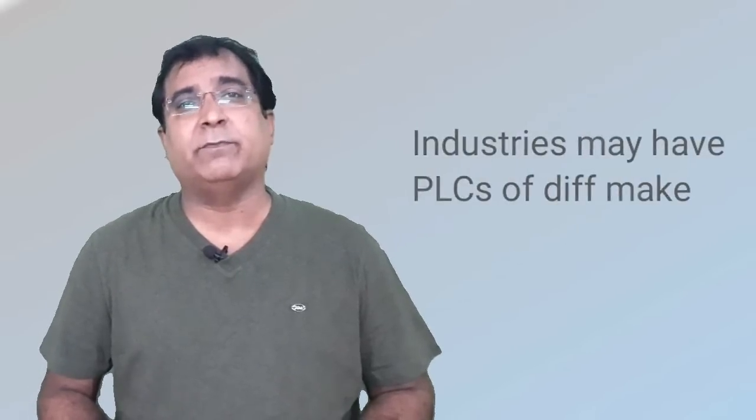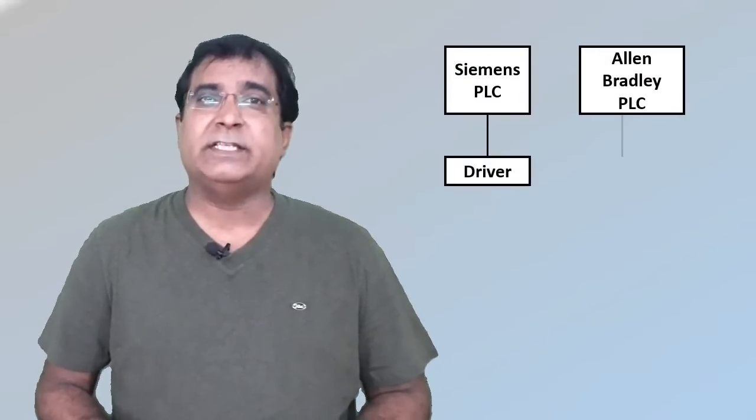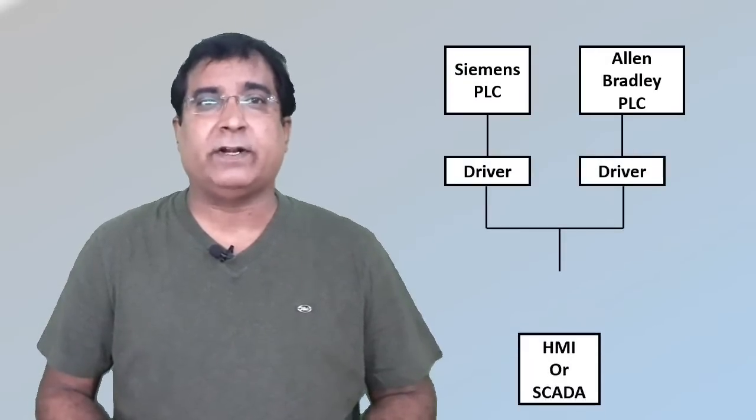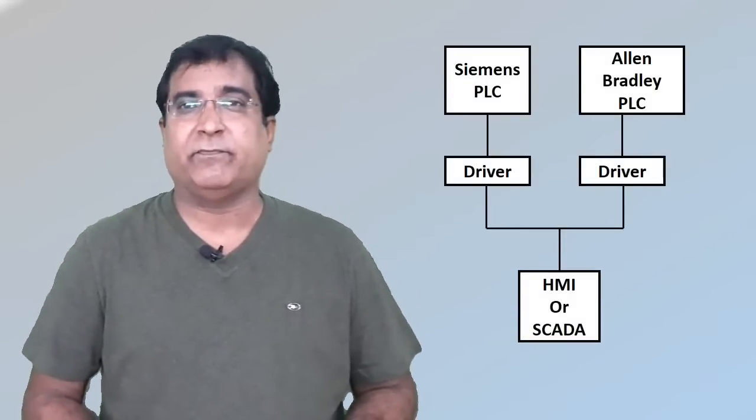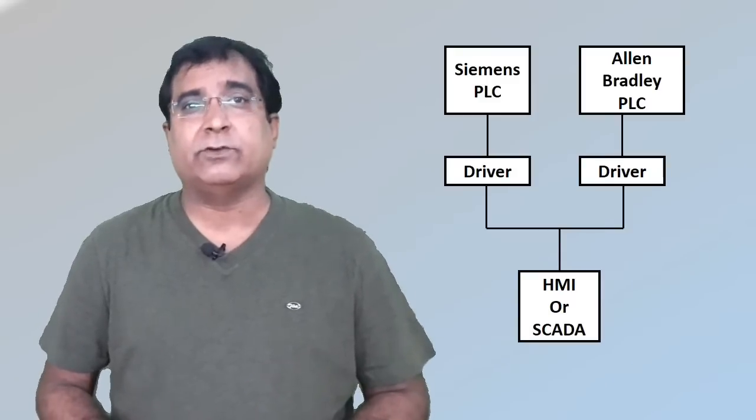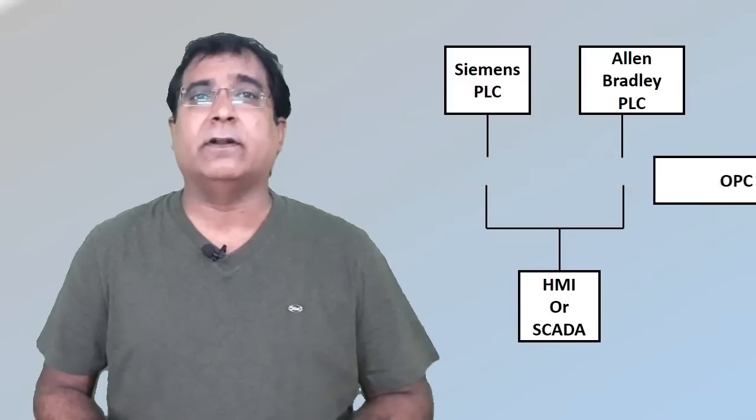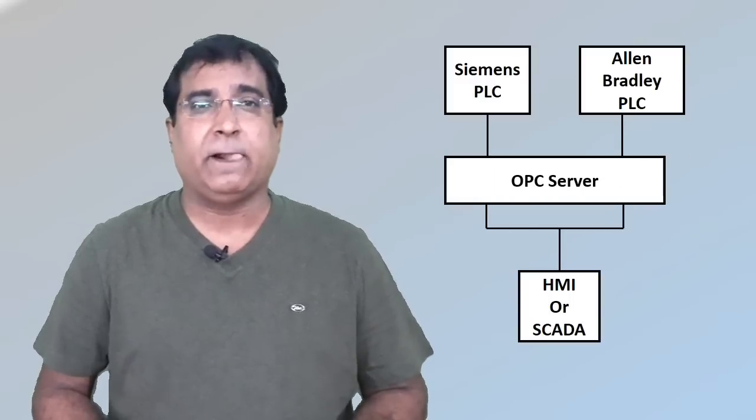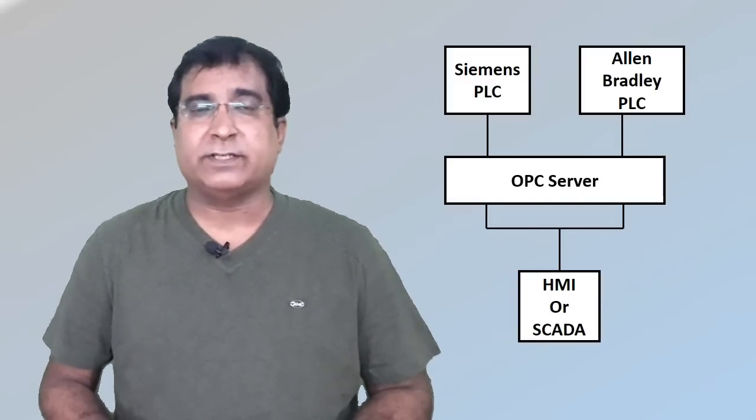We are communicating to the main plant SCADA or HMI system. These PLCs or control systems may be from different vendors like Siemens, Allen Bradley, Mitsubishi, or whatever. One way to connect these different PLC control systems to the main SCADA HMI is to use their proprietary device drivers. But these different device drivers cause loading effects on SCADA HMI applications. Also, when you add a new PLC or system, you need to have another driver and it carries cost. Here comes the role of OPC standard communication.